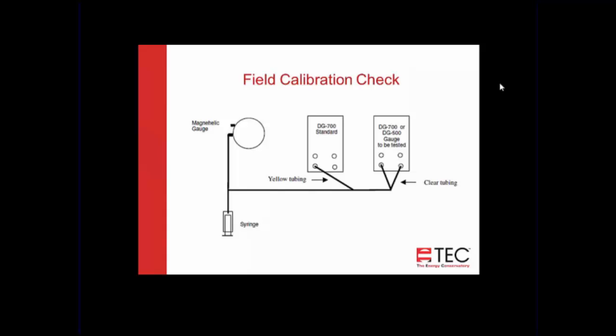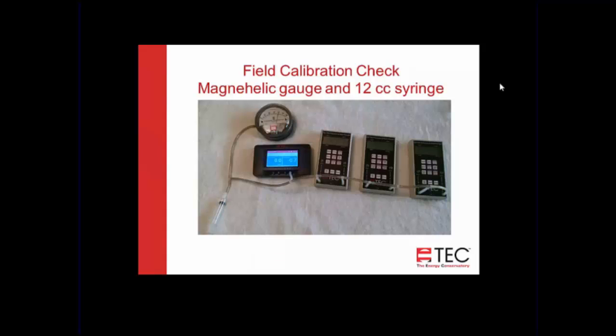We've typically used a 12 cc, 12 cubic centimeter syringe, or you could use one even larger than that because you've got the Magnehelic gauge for a buffer, and connect it up. You only need to connect up to one of the channels of the standard, and then both of the channels of the gauge being tested. And you're just checking to make sure that they're all reading within 1% of each other. So this is a picture of using a DG1000 for a standard and comparing 3 other gauges against that. So we've got the 12 cc syringe, the Magnehelic gauge, and a total of 4 gauges.